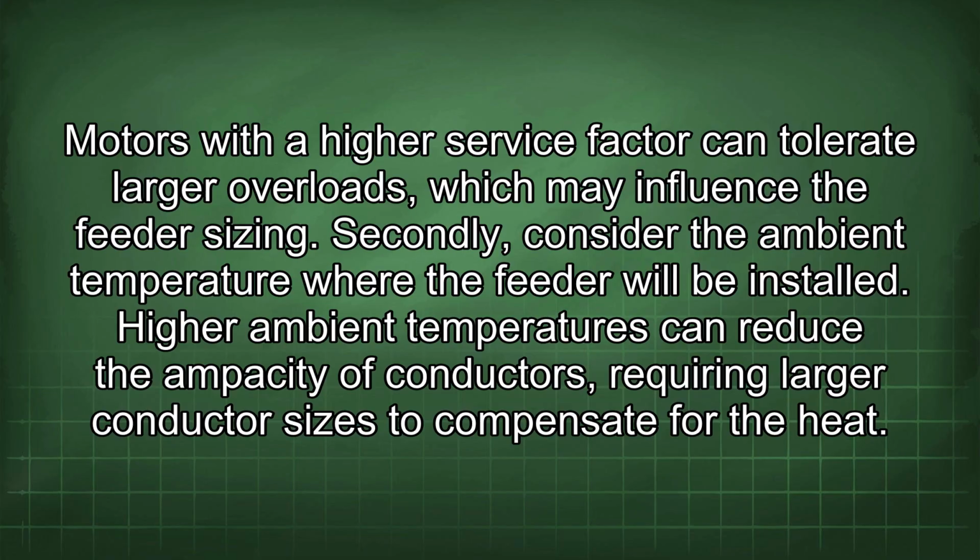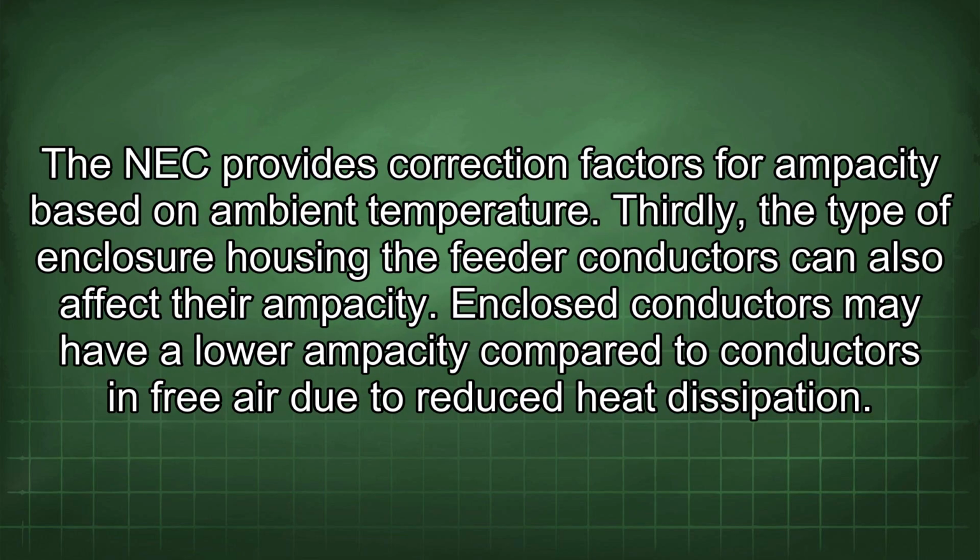Secondly, consider the ambient temperature where the feeder will be installed. Higher ambient temperatures can reduce the ampacity of conductors, requiring larger conductor sizes to compensate for the heat. The NEC provides correction factors for ampacity based on ambient temperature. Thirdly, the type of enclosure housing the feeder conductors can also affect their ampacity. Enclosed conductors may have a lower ampacity compared to conductors in free air due to reduced heat dissipation.